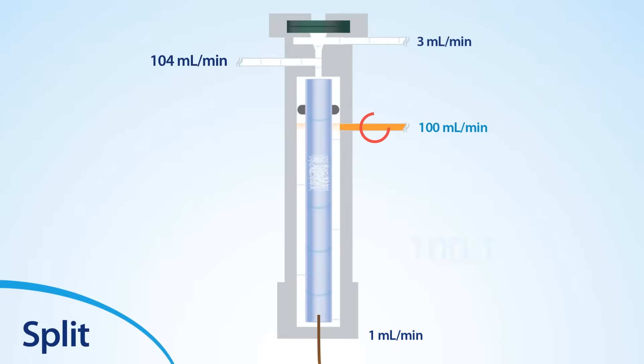During injection, the sample is injected into the liner and vaporizes. Since our example has a high split ratio of 100:1, one part goes onto the column, while 100 parts of the sample exit out the split vent.